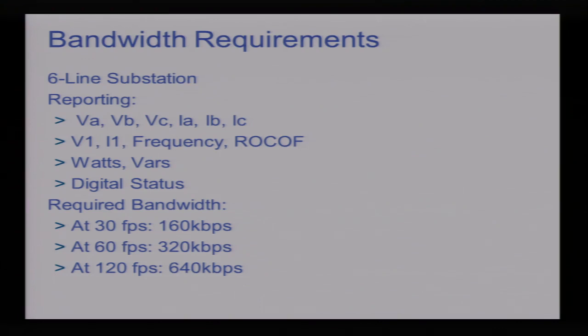In this case here, the frame rate dictates the bandwidth required. So if I'm sending measurements from my substation at 30 frames per second, and I'm sending VA, VB, VC, IA, IB, IC, V1, I1, frequency, etc., I need 160,000 bits per second of bandwidth on my communication channel. On the high end, if I go to 120 frames per second, I now need 640,000 bits per second communication from my substation to my remote locations.